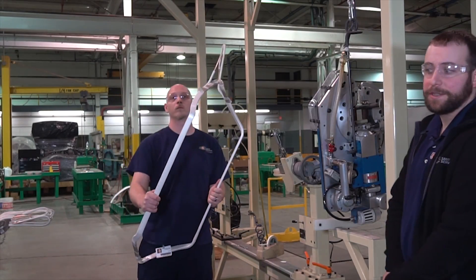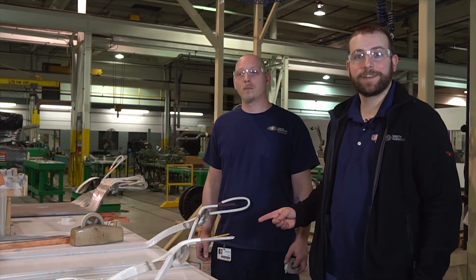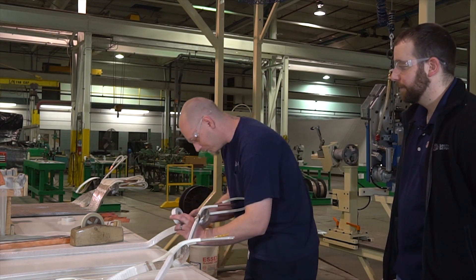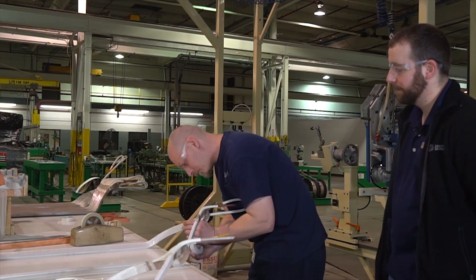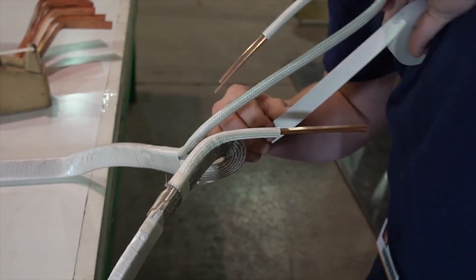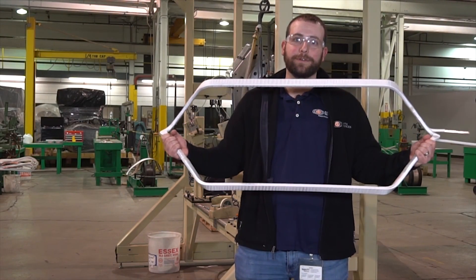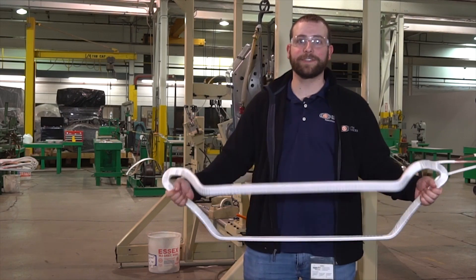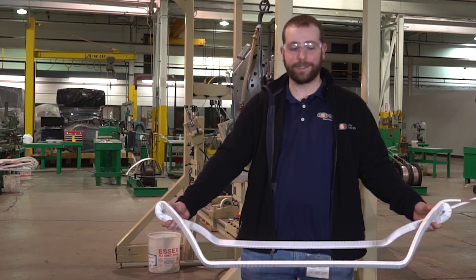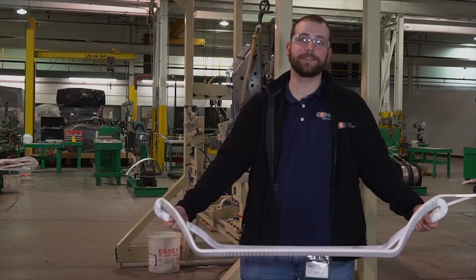This completes the insulating of our coil cells. After the coil is removed from the automatic taper, Zane will then finish insulating the coil by hand. So now we have our fully insulated coil. We've used our automatic taper to apply ground wall insulation to our cell. We've hand taped our knuckles with ground wall insulation and added armor tape to the overall coil. We're now prepared to go to our final step: electrical testing.